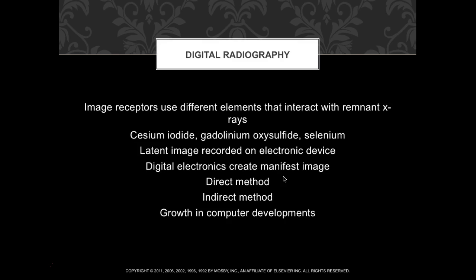In digital radiography, image receptors use different elements that interact with the remnant x-rays — the primary beam goes from the tube to the patient, the remnant beam goes from the patient to the image receptor. Elements used include cesium iodide, gadolinium oxysulfide, and selenium. The latent image is recorded on an electronic device, and digital electronics create the manifested image via direct or indirect methods.